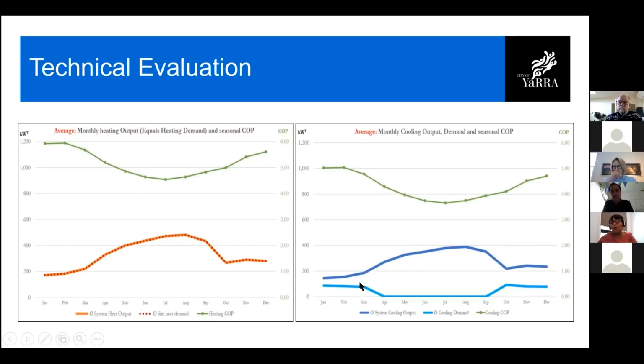And at the bottom, this is our actual cooling demand. So although we have multiple gym facilities and group fitness rooms, creche, offices, everything, this is how much cooling we need currently. So all of this additional cooling, including here in the summer months, can be utilized to cool the pool hall, or even to cool a nearby building. If you have a nearby council building, you can extend chilled water pipes, maybe an ice rink if you have one. The options are limitless, and this is absolutely free at this stage, because you're only paying to produce this. And these are the seasonal COPs, here for heating and here for cooling.